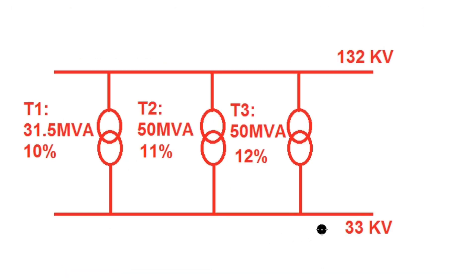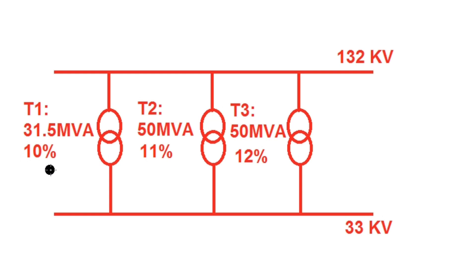Let us consider the example of three transformers operating at 132 by 33 kV. The HV side voltage is 132 kV and LV side voltage is 33 kV. For transformer 1, MVA capacity is 31.5 MVA with percentage impedance 10%; transformer 2 is 50 MVA with 11%; and transformer 3 is 50 MVA with 12%. We will determine the maximum load capacity that can be utilized from these three transformers.